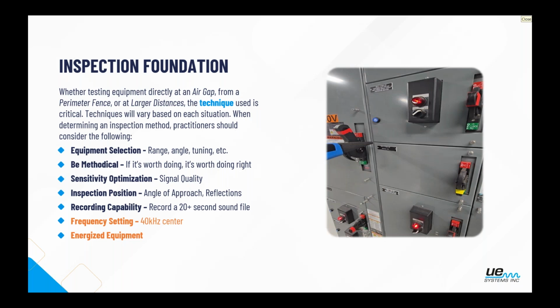And then, not necessarily a requirement, but I cannot recommend it strongly enough, is recording capability. I say not necessarily required because we can still do that go, no-go inspection. From the outside, are we hearing anything or not? But if we do hear something at that point and you can't record the sound file, you don't really know what's going on. You have to de-energize and do further inspection. Whereas if you can record that sound file, you know exactly what you're looking for.